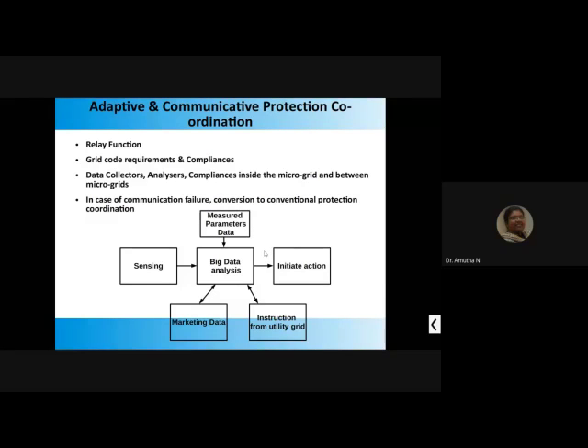Communication failure can appear, for example due to bad weather, causing interruption in communication. If communication breaks, the relay will stop working. In that case, if there is a fault, it will not be able to detect it, and the entire system may collapse. So the system has to be built on the conventional protection coordination as a base.